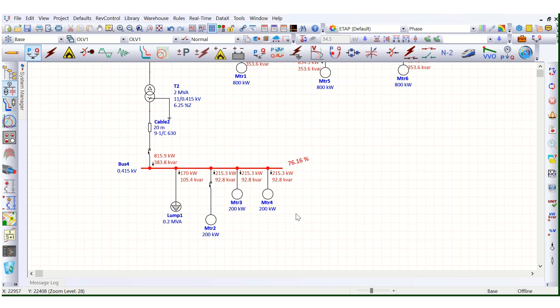The first thing to check is the connected load — whether the loads connected are already oversized, or very large rating motor loads or lump loads are connected. If so, you need to shift those loads to another board, another switchboard, another MCC, so that this error will be removed. This is a fundamental principle when developing a power distribution network.